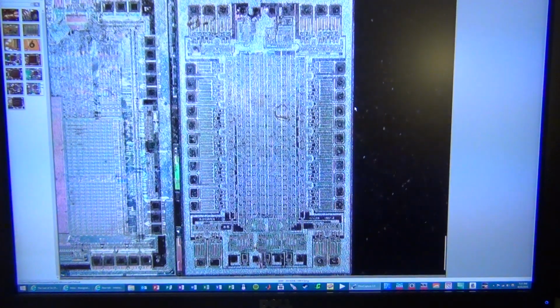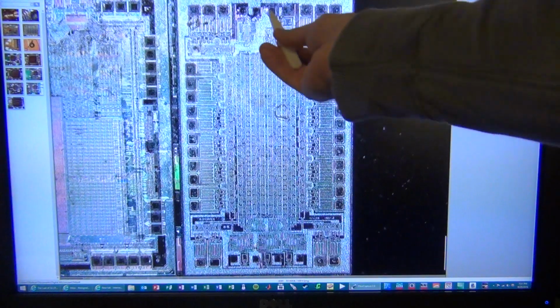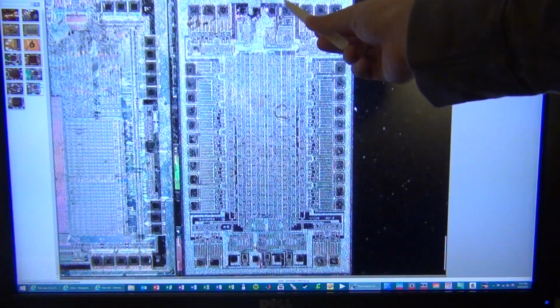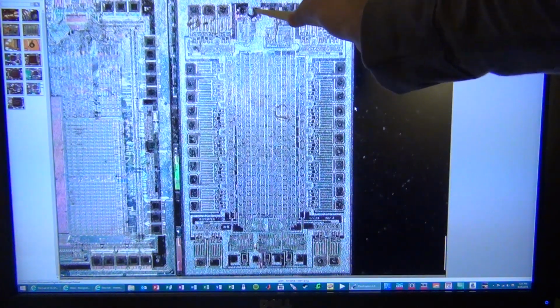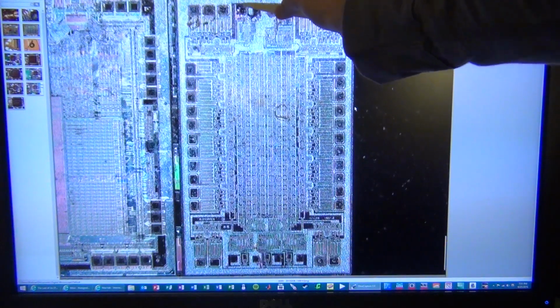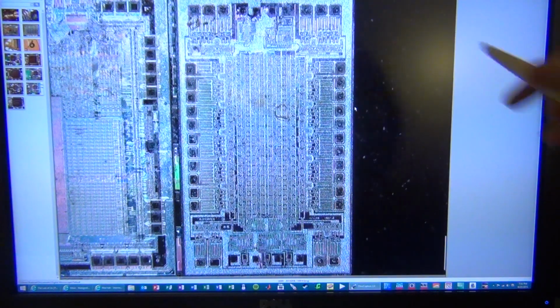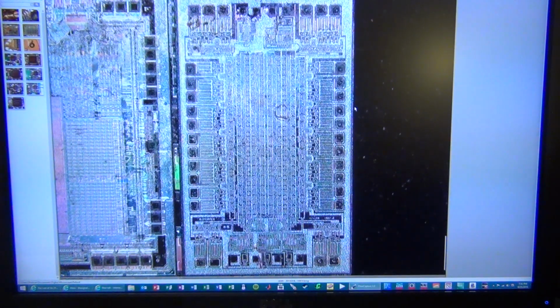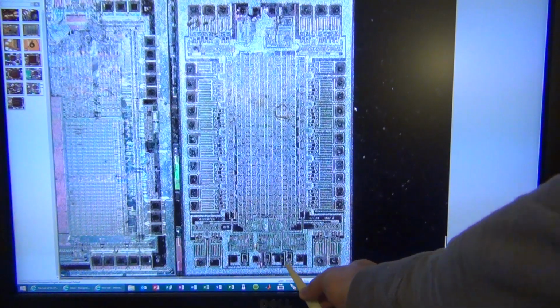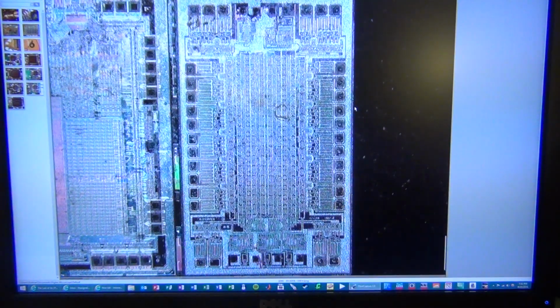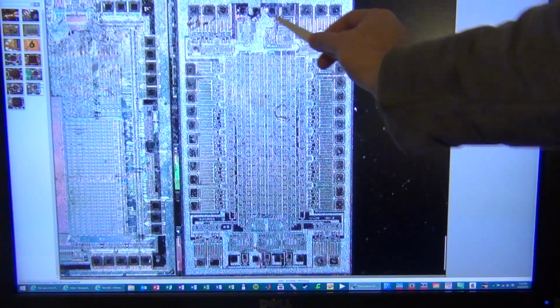And if you recall from the original video, there was a short between the high voltage VFD driver power supply and the 5-volt I/O power supply. And that is right over here. If you pay close attention, you can see that there has been a bridge, a gap between these two, creating a short circuit. And that short circuit, of course, then went ahead and damaged all of the other circuits that were on the display driver. Everything else looks pretty good. There seems to be some minor damage here as well. But this, I believe, is the main point of failure.